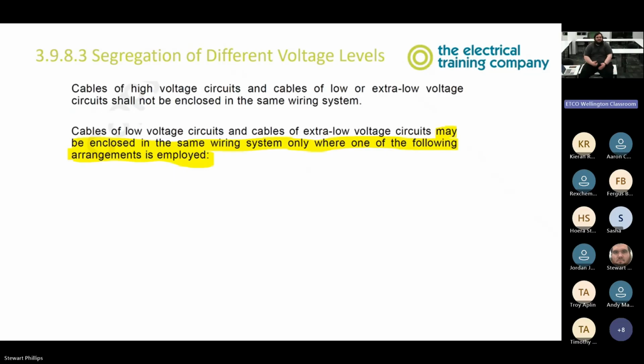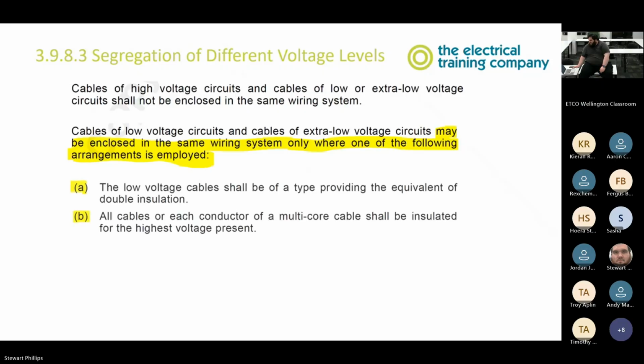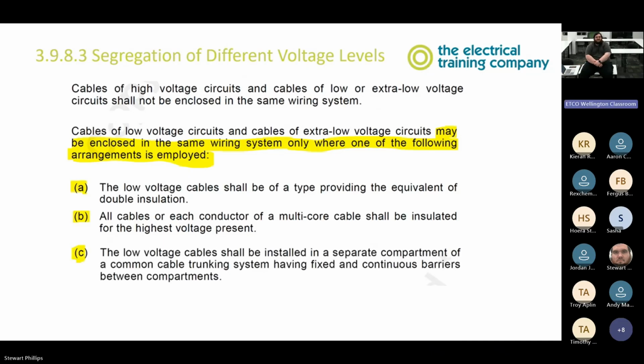Cool. Cables of high voltage circuits and cables of low or extra low voltage circuits shall not be enclosed in the same wiring system. So they may be enclosed in the same wiring system only when one of the following arrangements is employed: for low and extra low, not high and low. Low voltage cables shall be of a type providing the equivalent of double insulation. All cables or each conductor of a multi-core cable shall be insulated for the highest voltage present. The low voltage cables shall be installed in a separate compartment of a common cable trunking system, having fixed and continuous barriers between compartments. So that 2-part trunking that we saw before, we can have one half with power and one half with data. It's not recommended, but it is allowable.